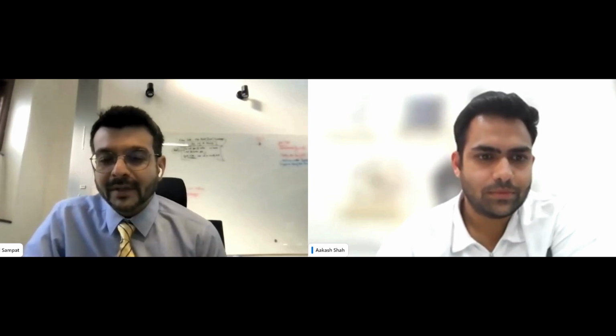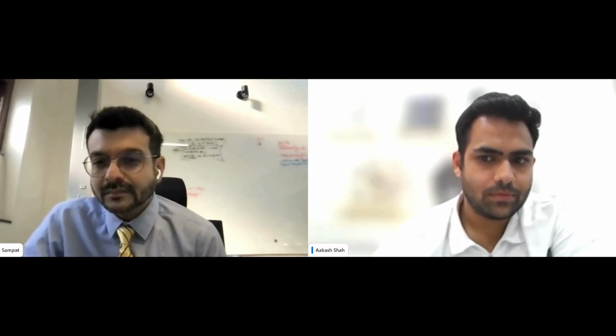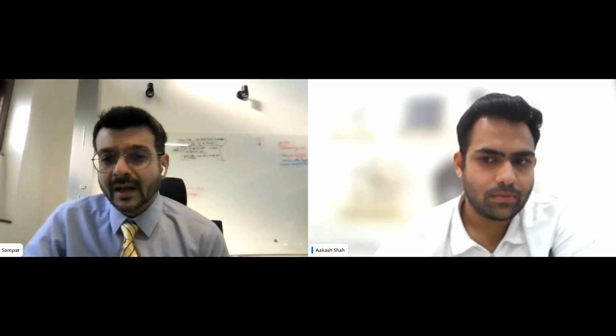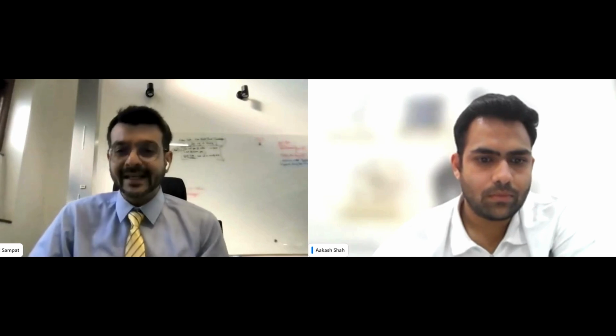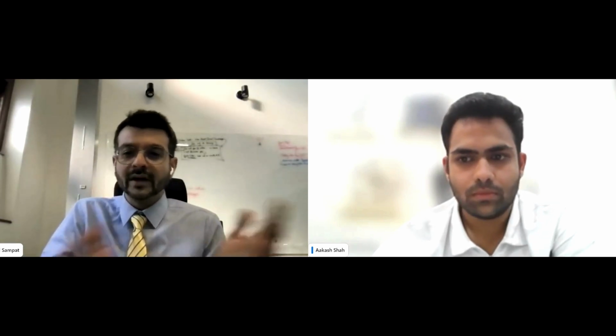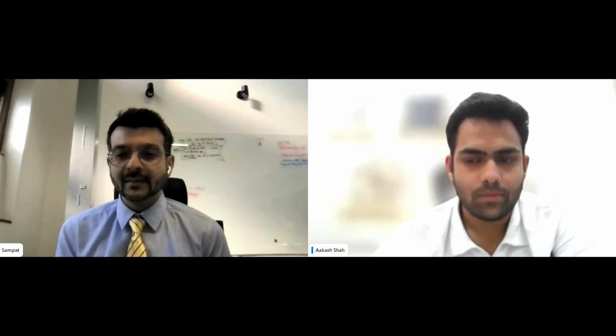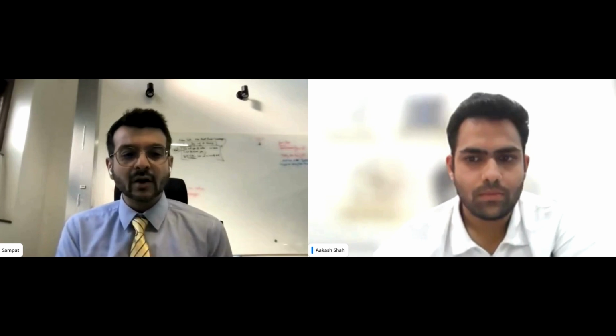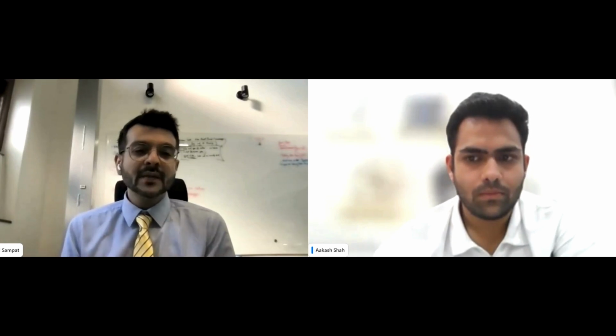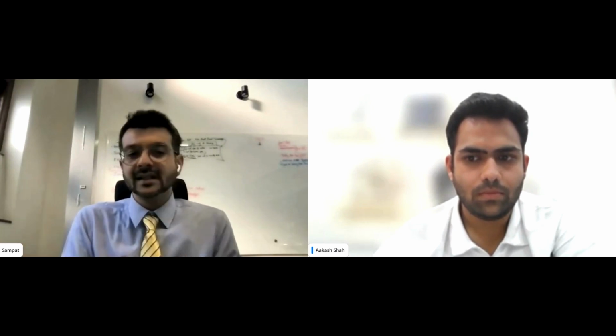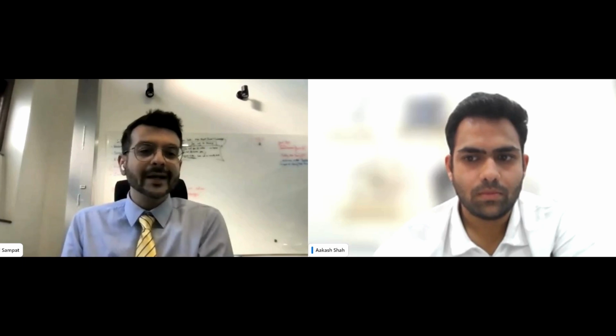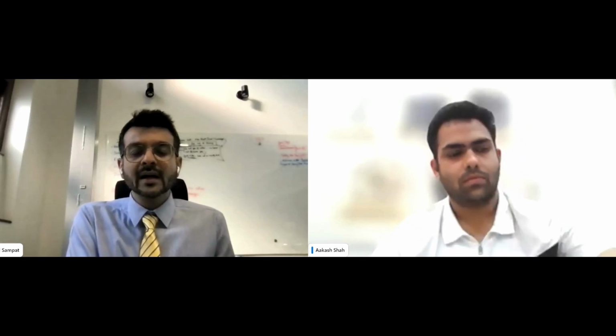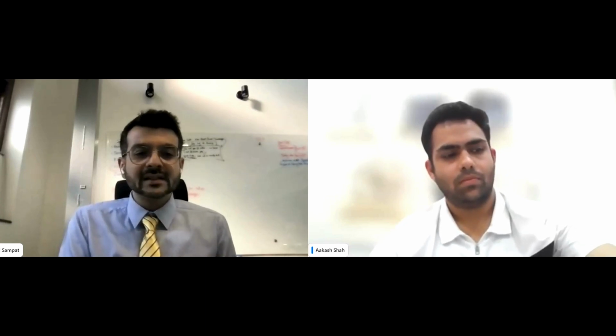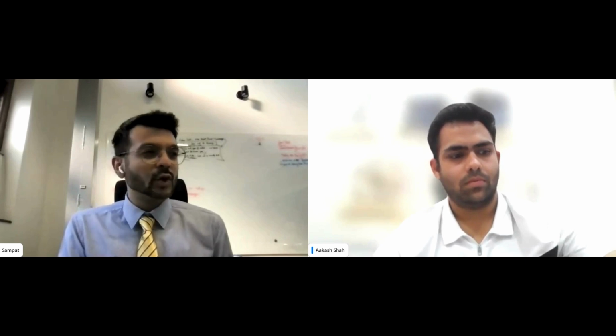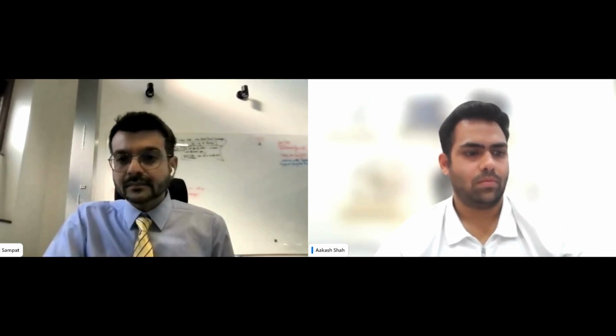Pratik Patel, sir, from Ahmedabad, our partner there, asks: if the DG set runs for 24 hours, will LPG consumption make it cheaper to run in dual fuel mode? Yes, it will be cheaper compared to 100% diesel mode, because you're replacing a lot of diesel with LPG. The cost difference between LPG and diesel is currently about 20 rupees — 1 liter of diesel is approximately 100 rupees, and 1 kg of LPG is about 80 rupees as per current market price. So it will save cost in that aspect.